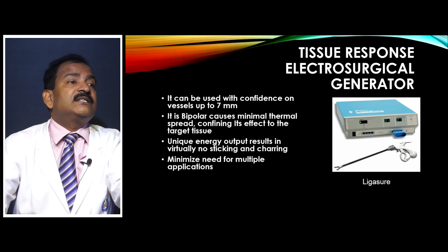And you do not need multiple applications, opening the jaw and catching again, because there will be less scar formation, and there will be no chance of sticking to the jaw, because it is not overcooking. So, due to these reasons, it is a very good vessel sealer. It is a good vessel sealer, but it is not a good dissector. If you want to cut the serosal layer of a myoma, LigaSure will not do that, harmonic will cut. If you have to do colpotomy, LigaSure will not do that, harmonic will do. So harmonic is a good dissector, LigaSure is a good vessel sealer.